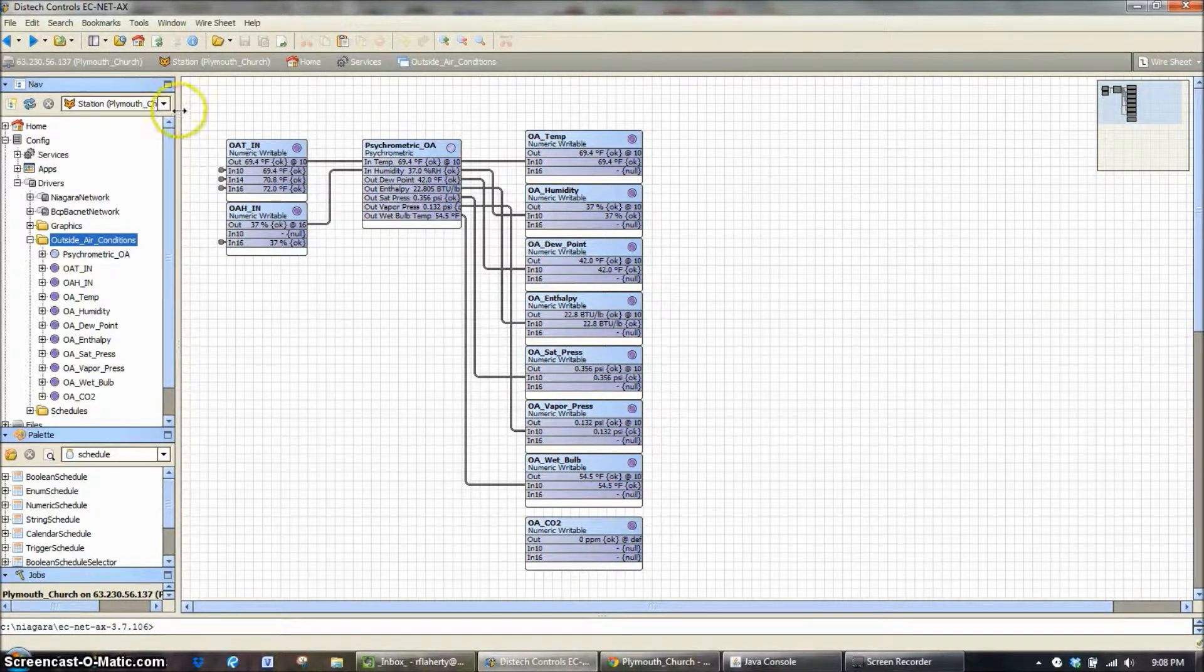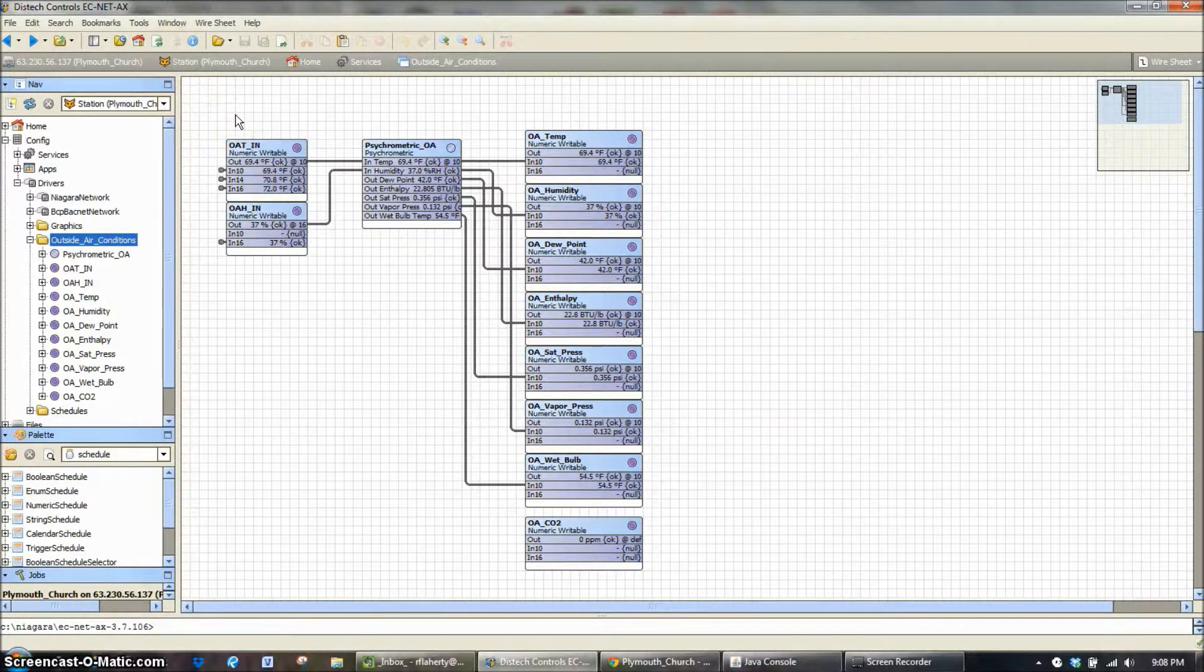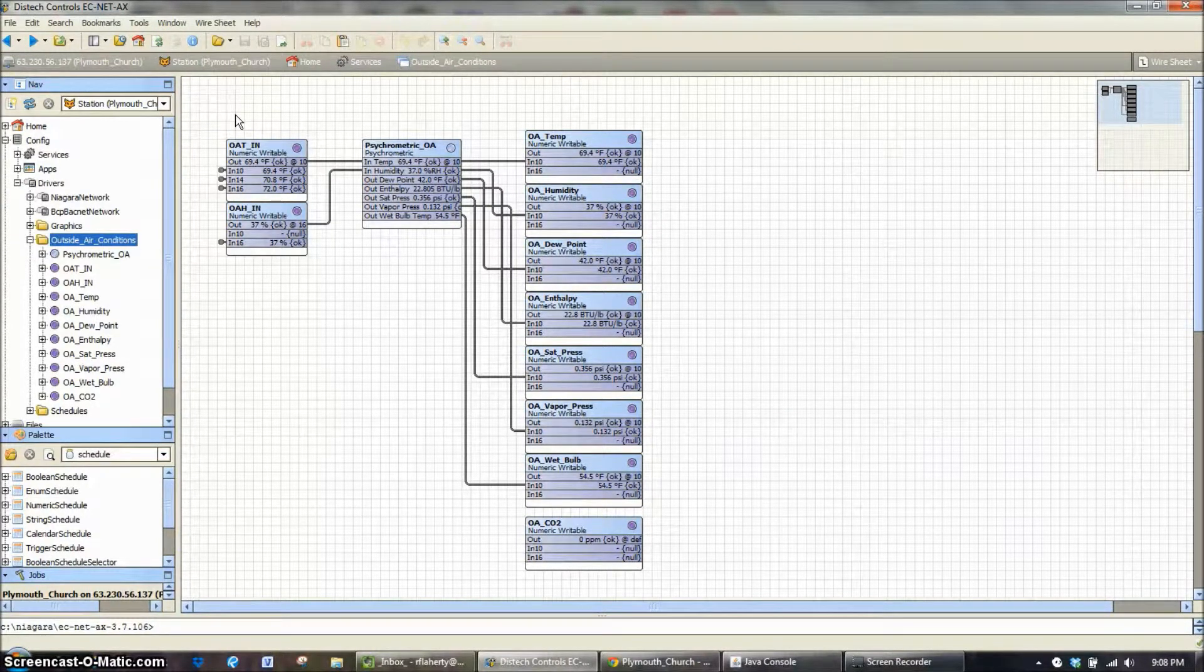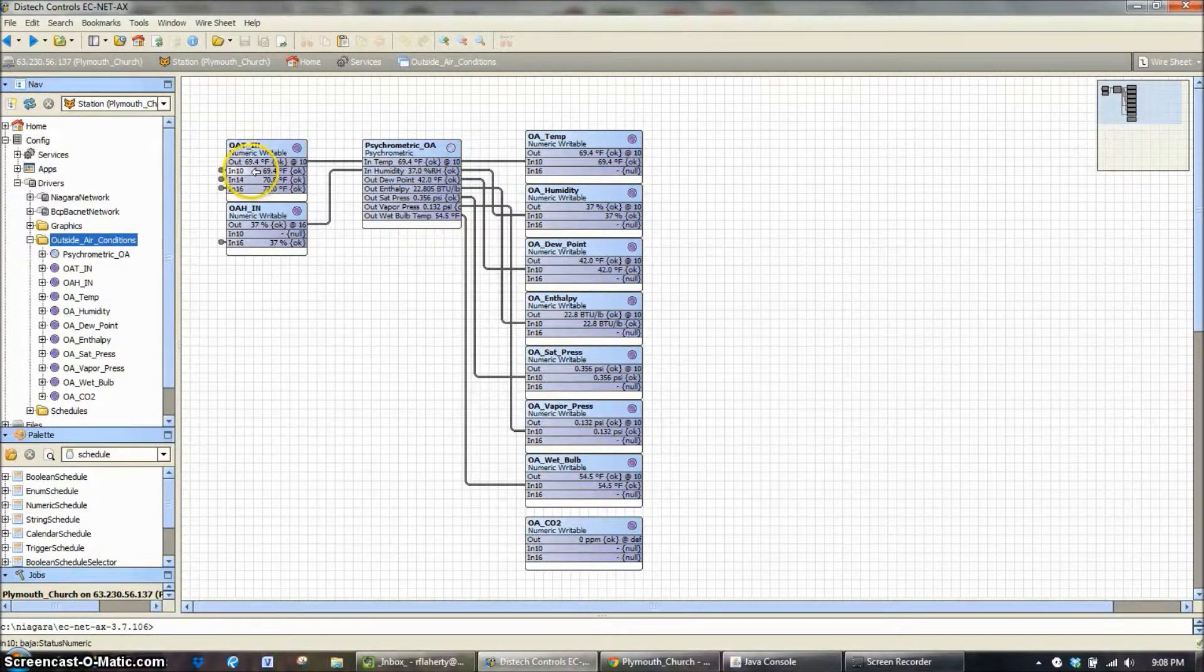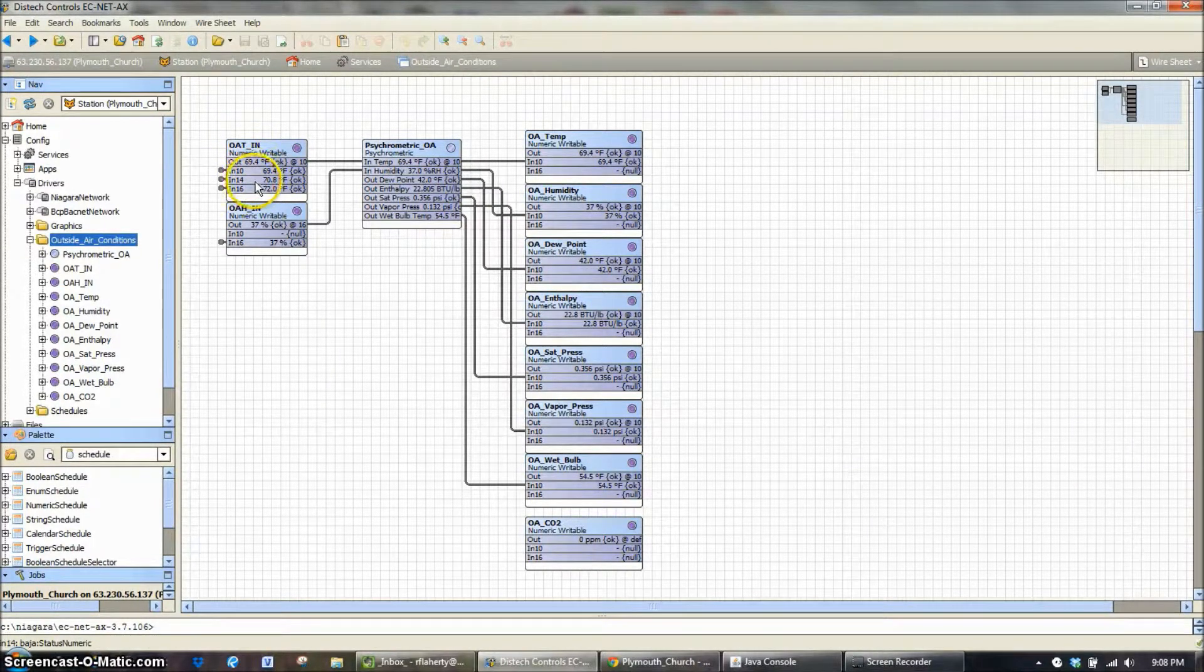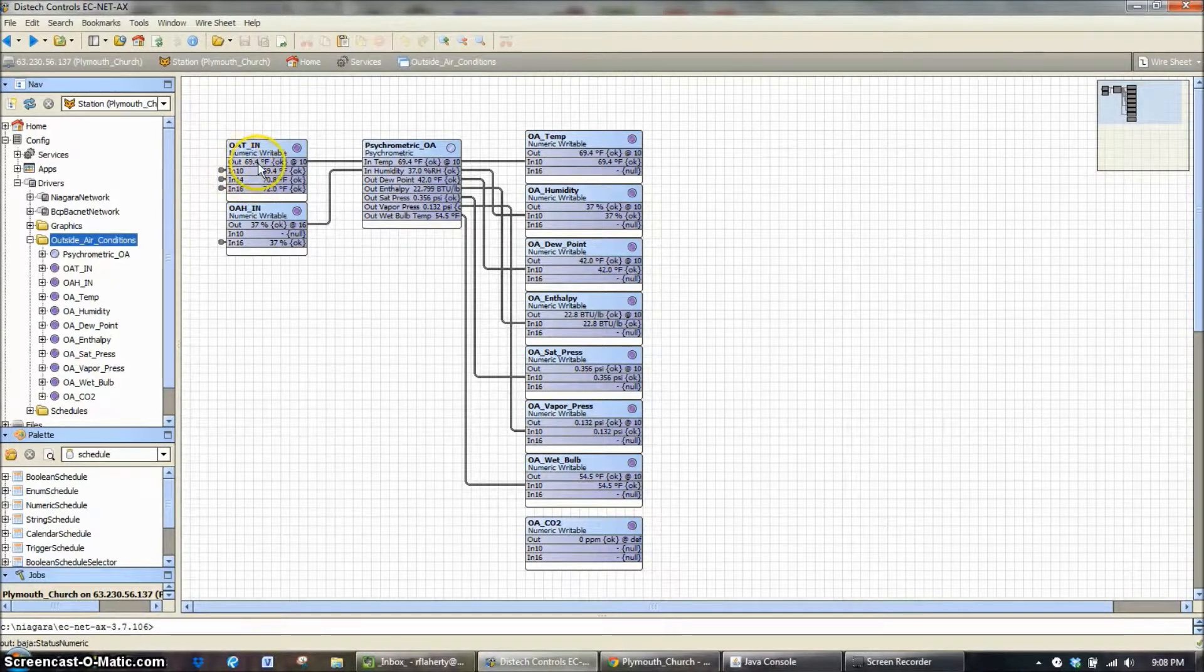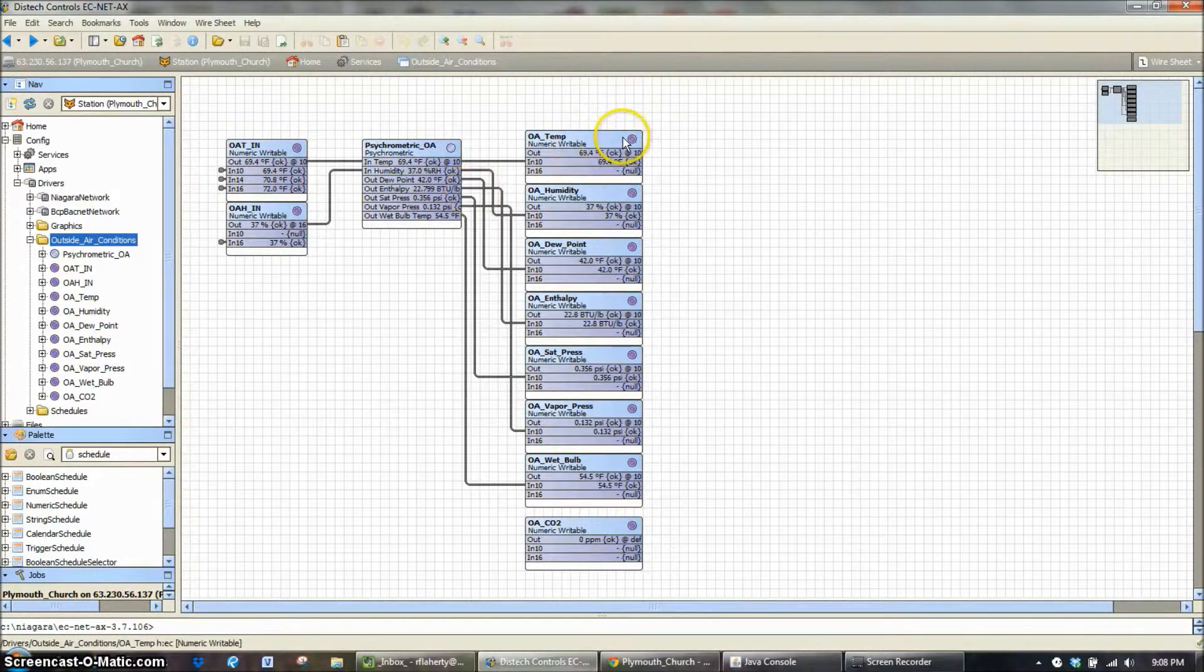So, if input 10, let's say our make-up air unit, someone goes up to use that unit, or to go up and service that unit, so they throw the disconnect on it, it kills the power to the control system. This will turn yellow and turn offline, and it will roll over and start using input 14. So you'll start to display an output of 70.8 degrees, which gets fed into our system.